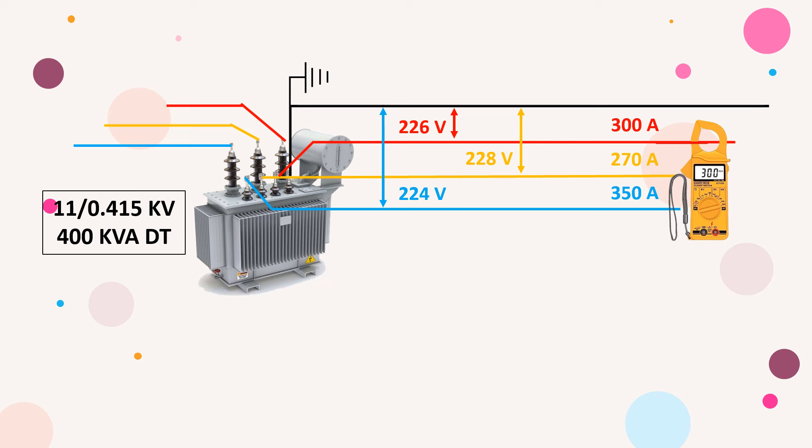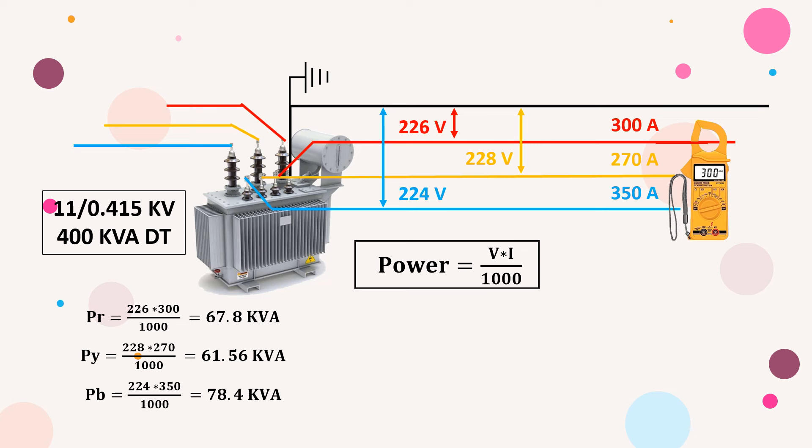That means active as well as reactive load. So just multiply voltage and current in each phase and divide by 1000. It will give you the total load connected on each phase in kVA.